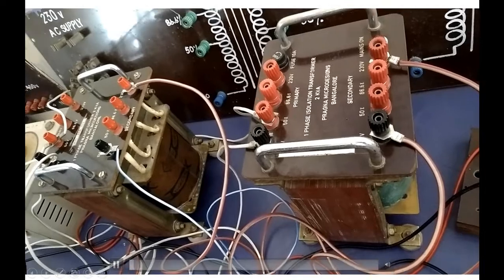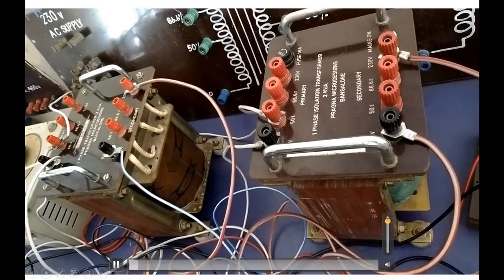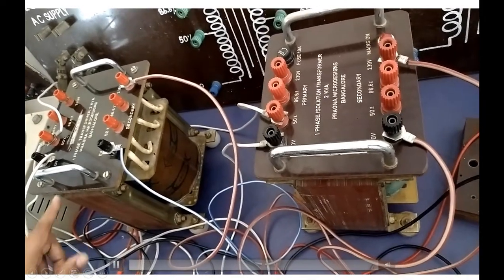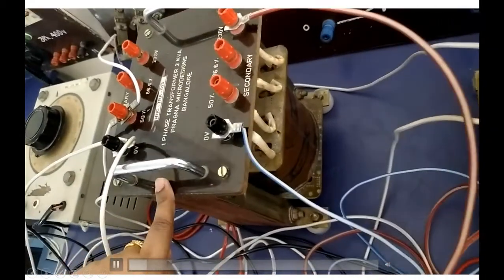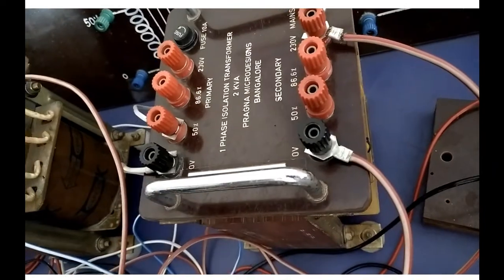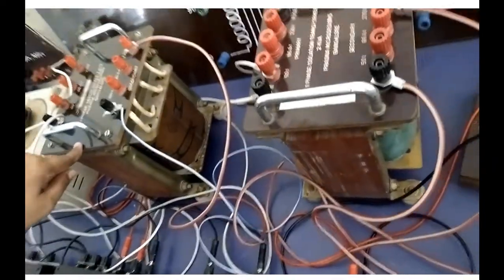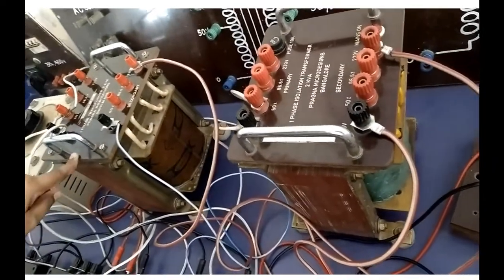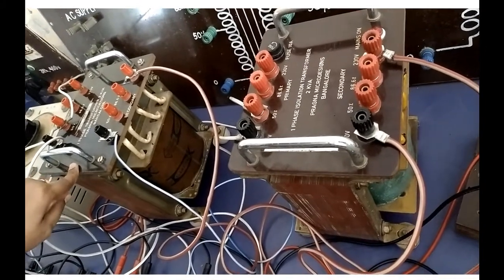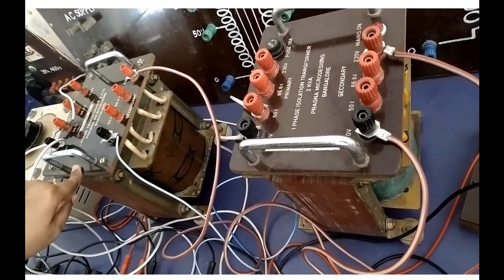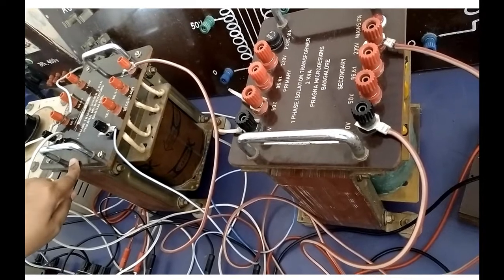We are going to perform Sumpner's test. Sumpner's test is performed on two similar transformers. So see here, a 2 kVA transformer and the next 2 kVA transformer we are taking, and we are going to perform the back-to-back test, that is Sumpner's test, to predetermine the efficiency and regulation at any power factor at any load.